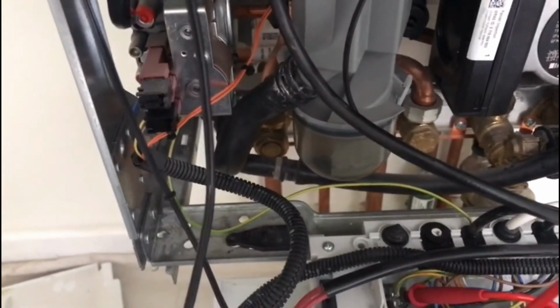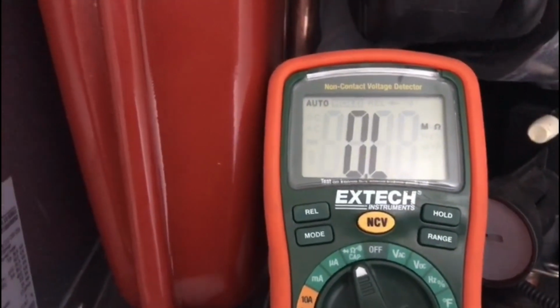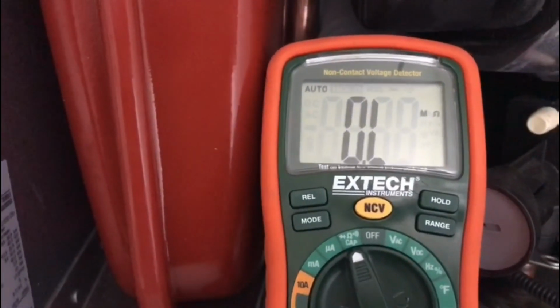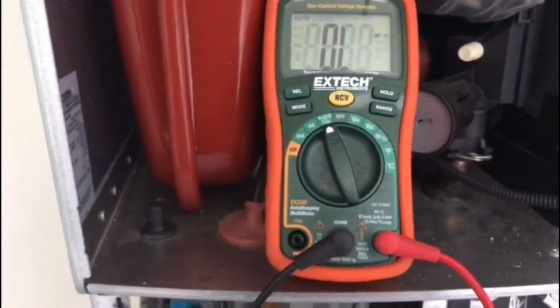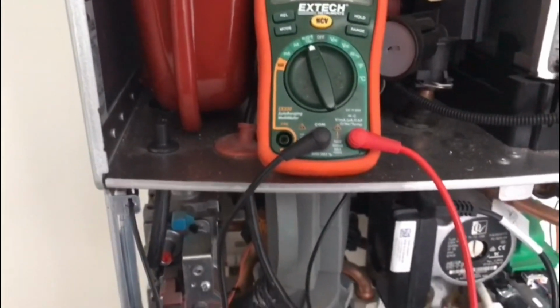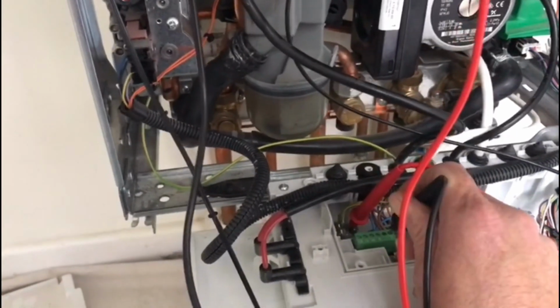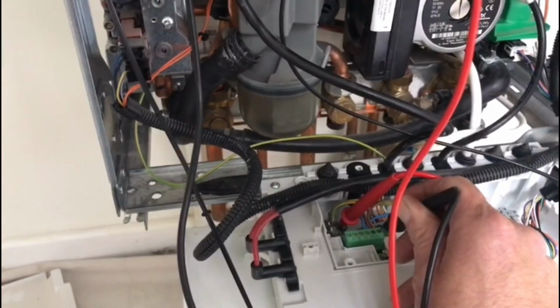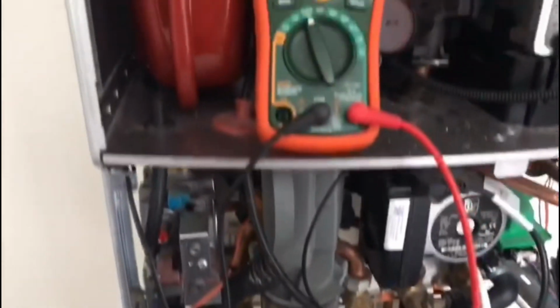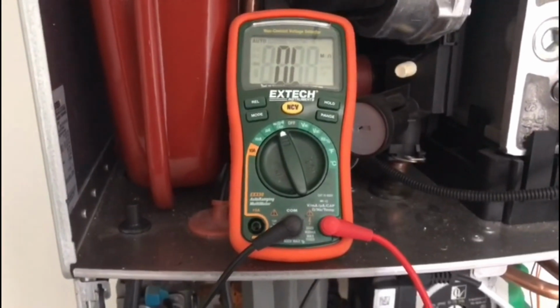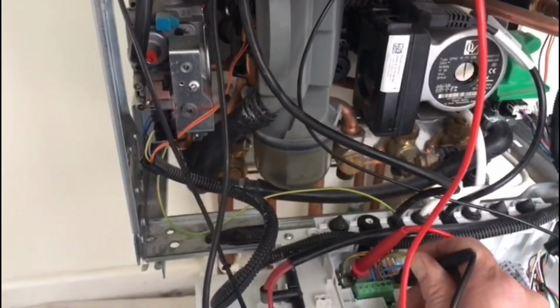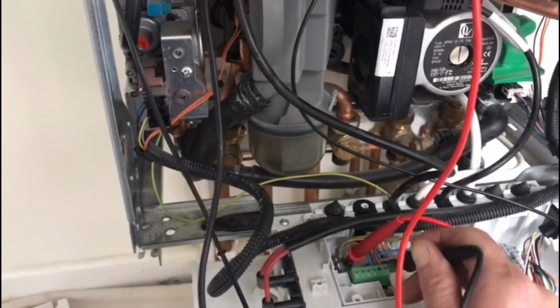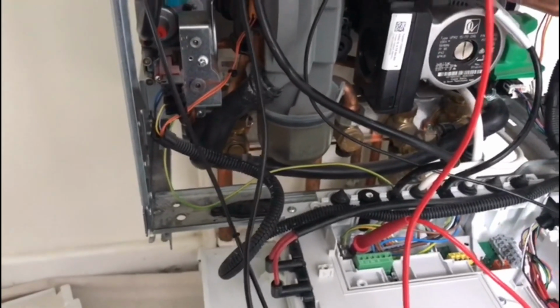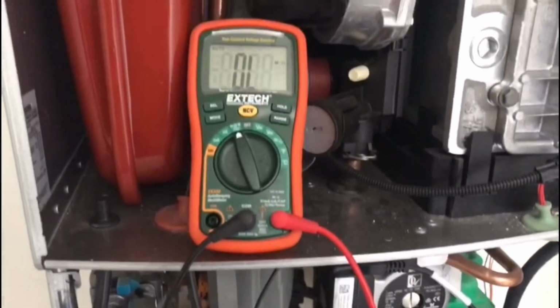So with your probe on your earth, you test live to earth. You test on your live pin, and your reading should be open line. In other words, there's no way those two wires are actually connected. You should get a reading larger than 1 megaohm, which is 1,000,000 ohms. So obviously you've got to make sure that that is the correct reading. If you're thinking, oh, there's something wrong, I've got open line, don't think that. Open line is correct. Open line is the best reading you can get on a resistance to earth check. Make sure that your live and your earth are completely separated, so there's no path down the earth from any live current when the boiler's in operation.